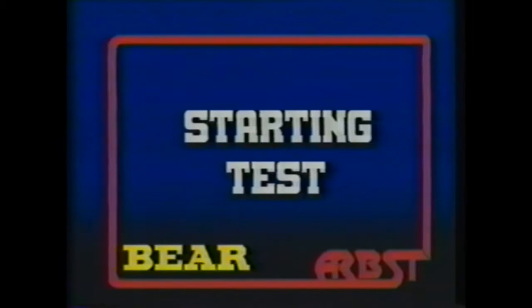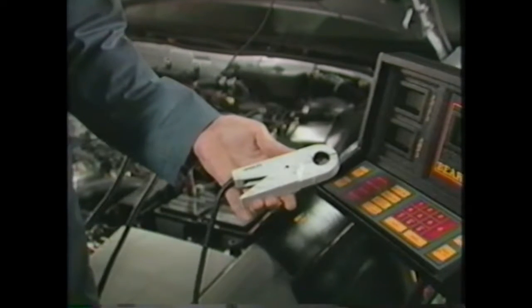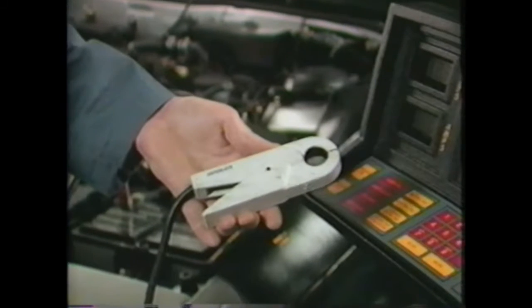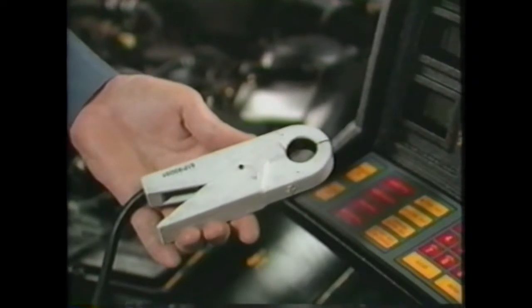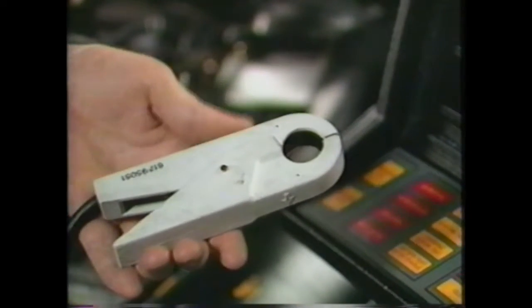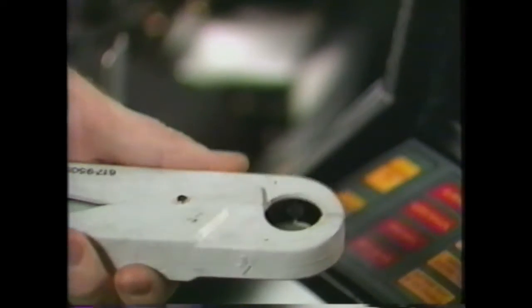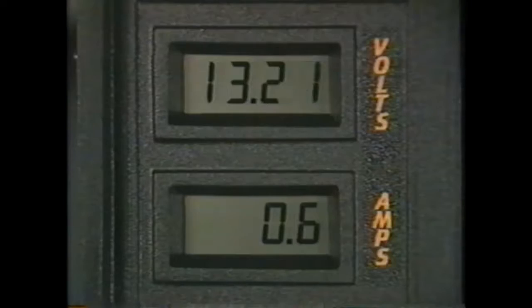Now that we're finished with the battery test, let's perform a starting test. The starting test uses another lead, the gray amps probe. We recommend that you perform a simple procedure to zero this amps probe before each starting test. The procedure sets the probe to zero in much the same way that you might zero a scale, so it ensures the accuracy of the amps readings during testing, and it only takes a few seconds.